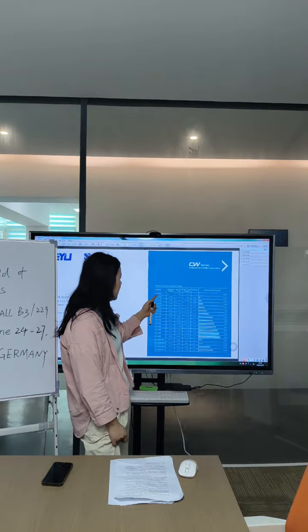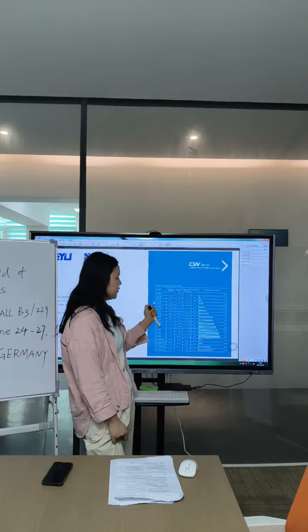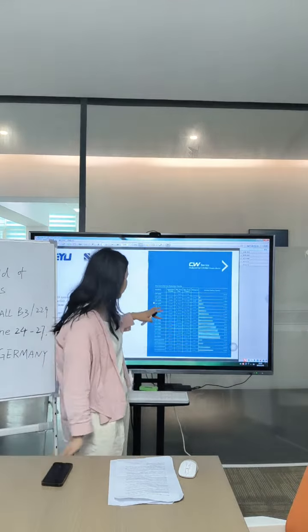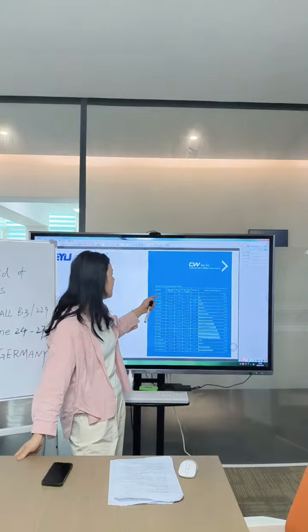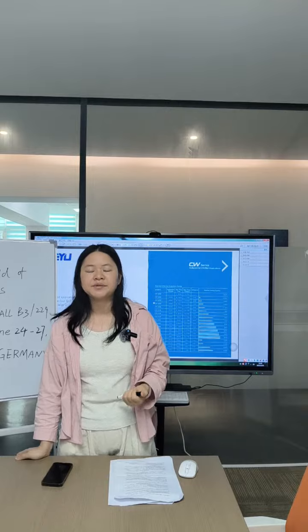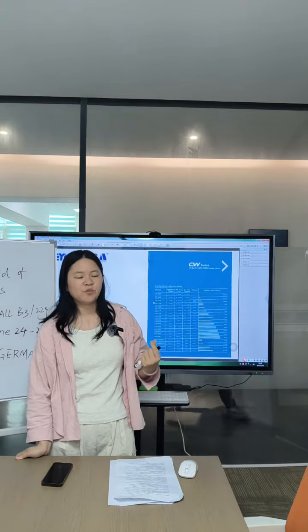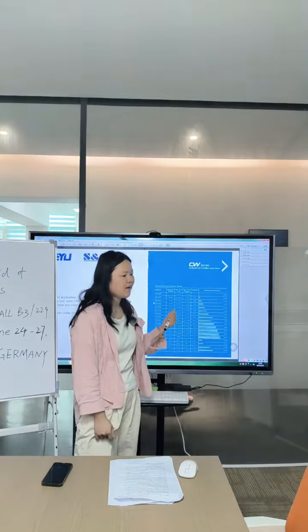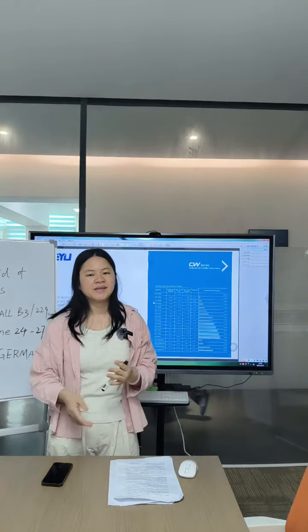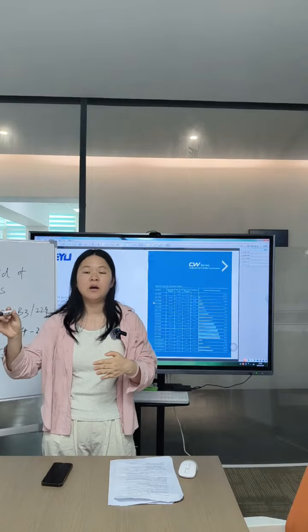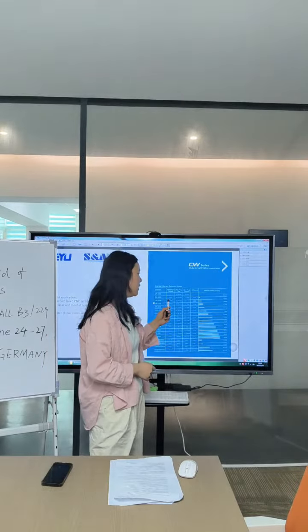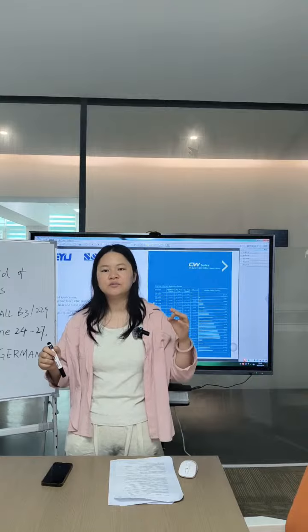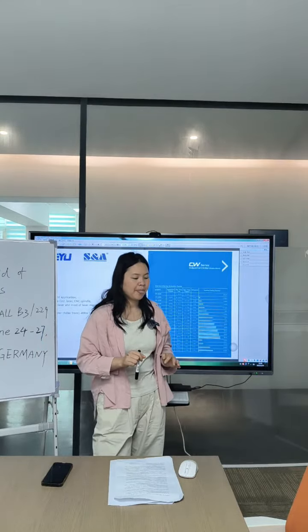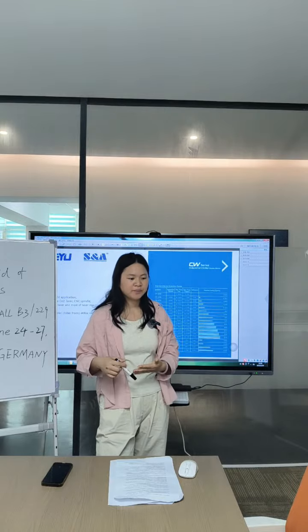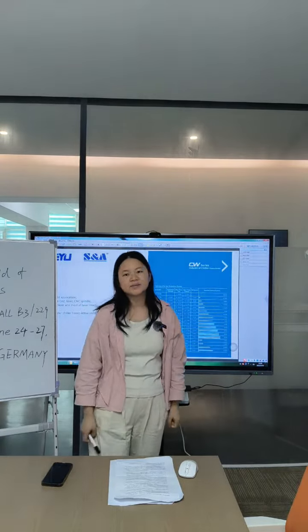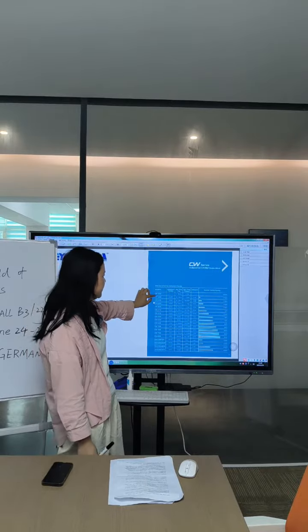Here I want to mention the CW3000 model. It is very special compared to other models because it is the passive cooling type. What does that mean? This model has no refrigerant and no compressor. It's passive cooling, relying only on fans to dissipate heat. So it's very special, but it also cannot control the temperature. If you need to set your water temperature, you should consider another model. That is the difference with the CW3000 model.